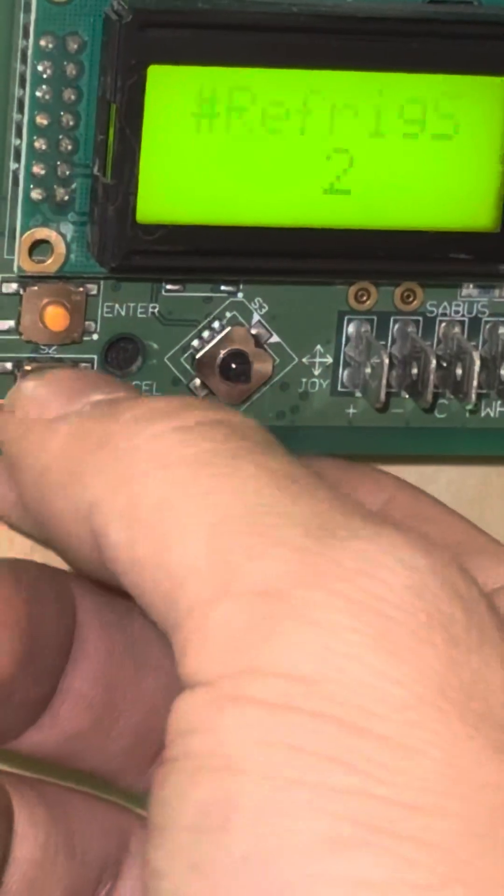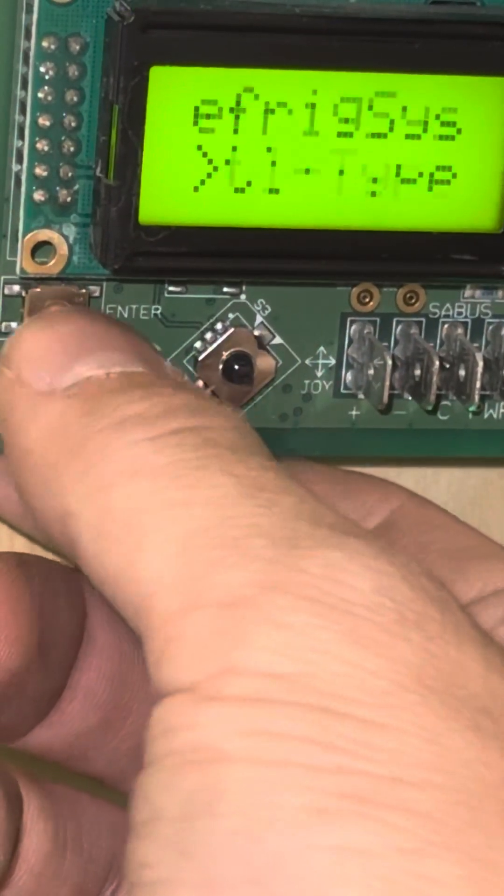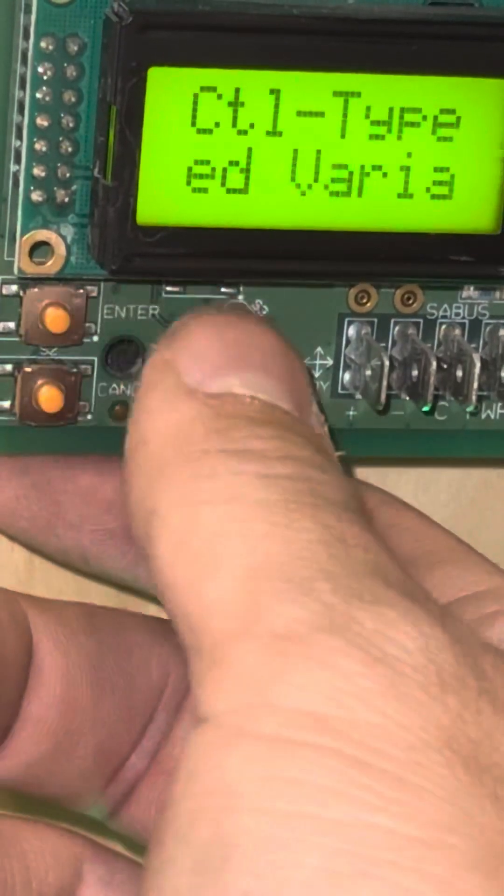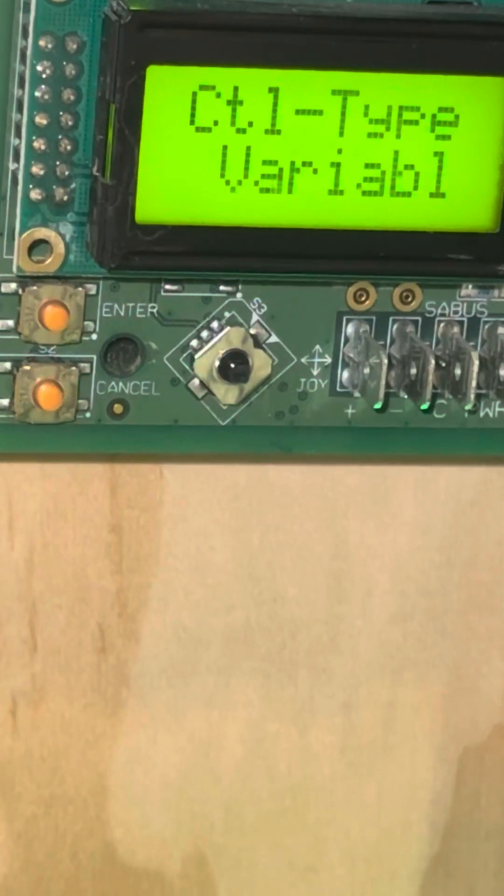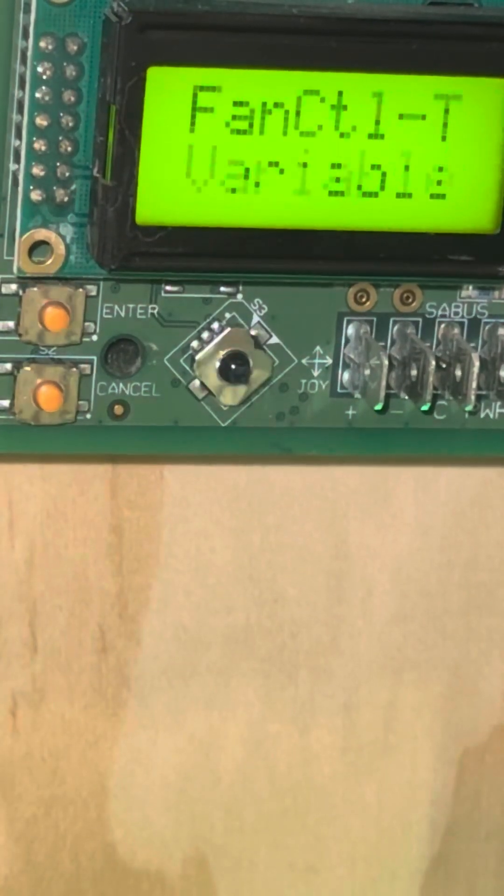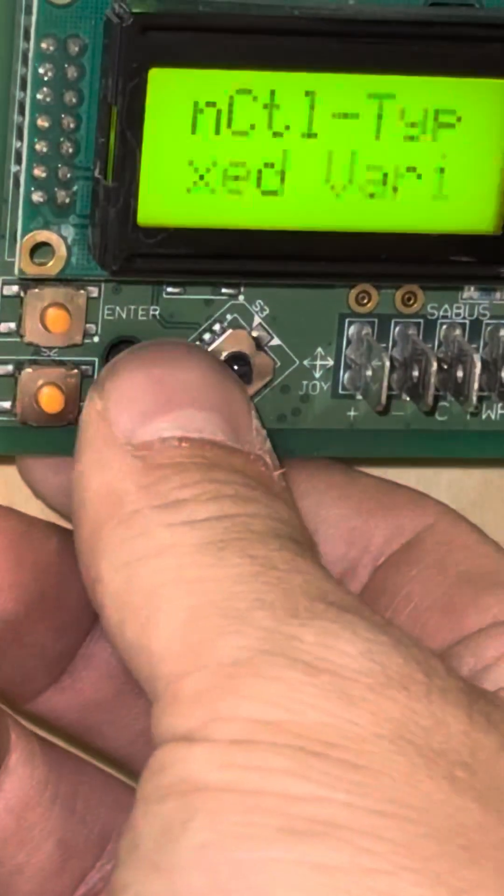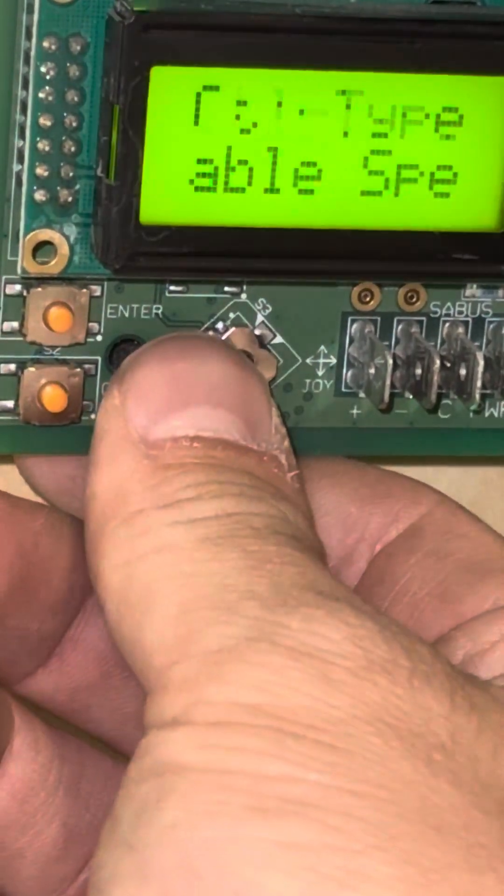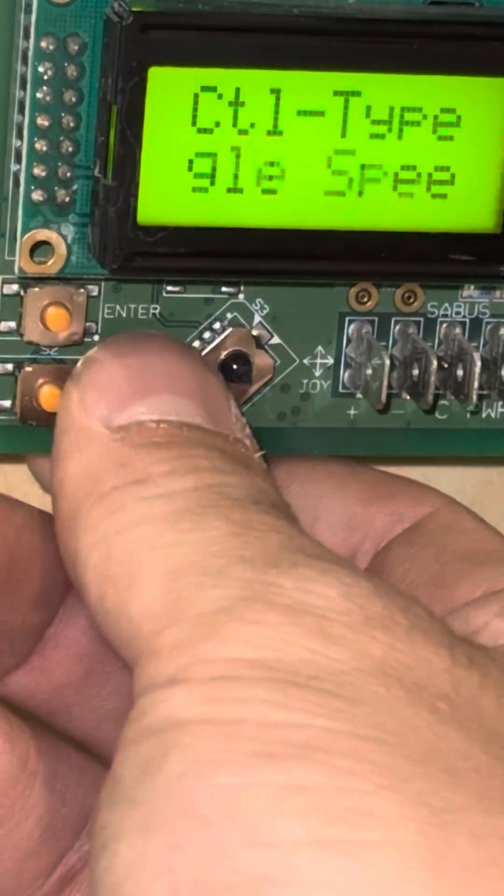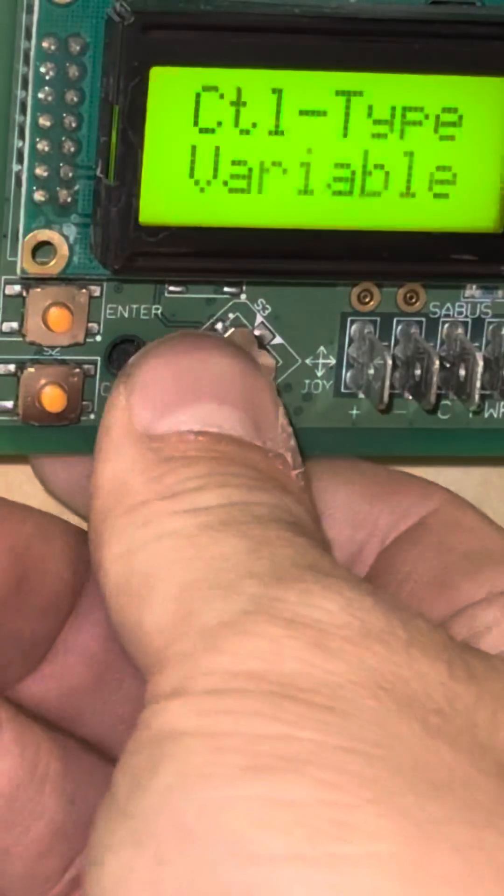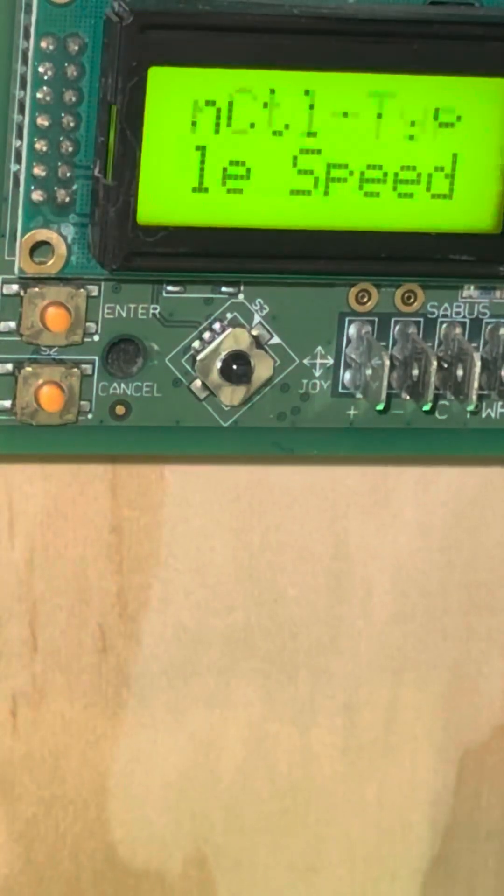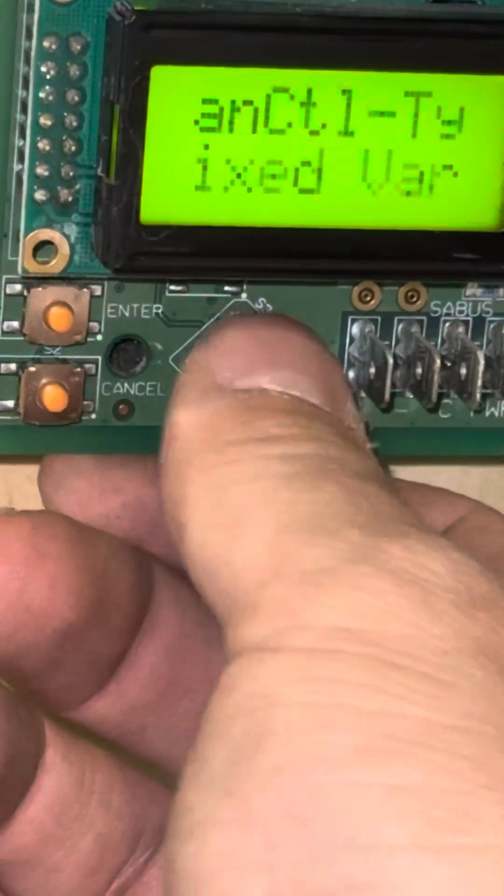My fan control type, fan CTL type, I'm set to fixed variable, which basically means I have a constant volume application with a VFD. If I had constant volume with single speed, I don't have a VFD in my unit, then I'd want to press enter and change that to single speed. Now it's displaying single speed and it's flashing. The third option would be just variable speed, and that would be for VAV applications.